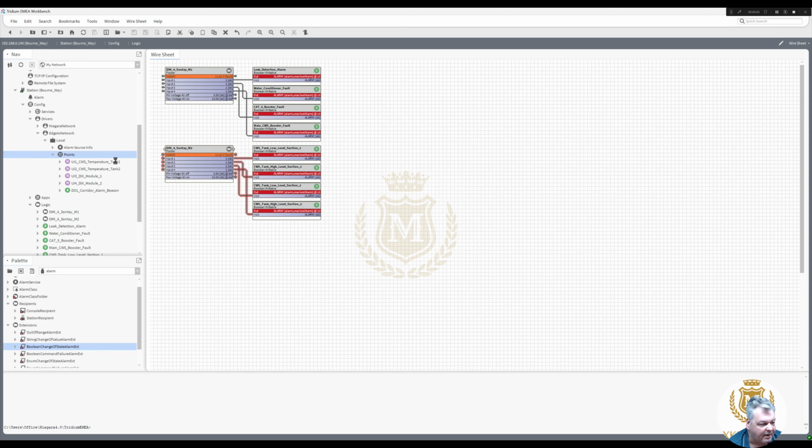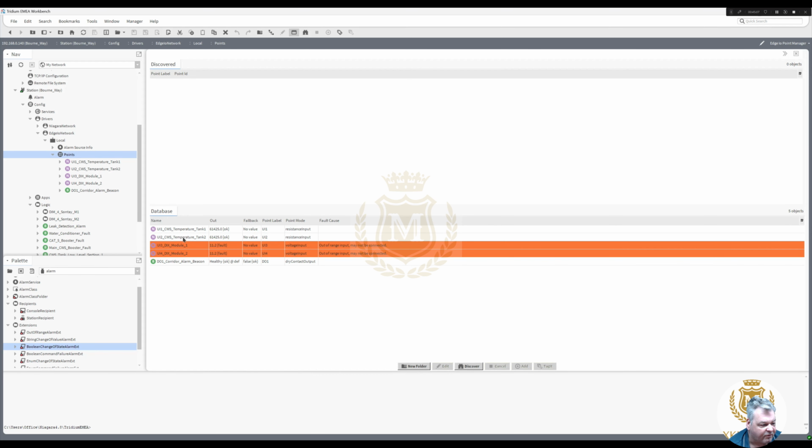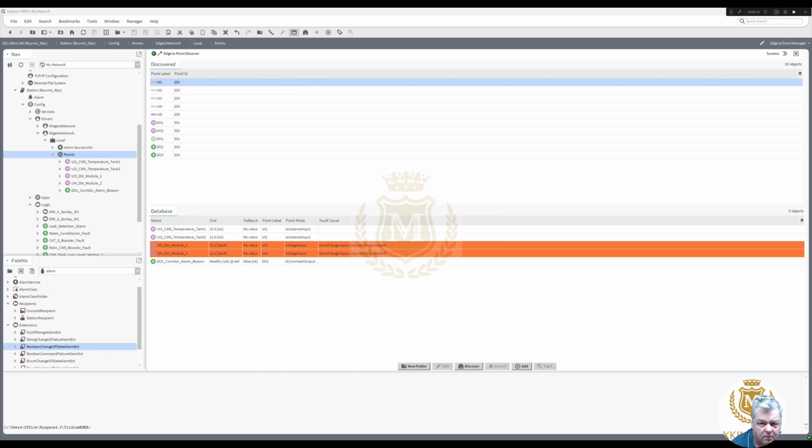Now I'm thinking about these here. I think I'm going to put a temperature sensor, physically connect one to this controller so you can see. Should be 10K3A1s. So let me put you on pause and let me just connect the temperature sensor. So I've installed two temperature sensors, outdoor temperature sensors. So that's done for that.